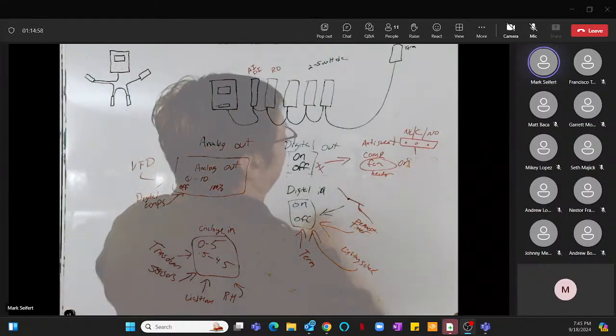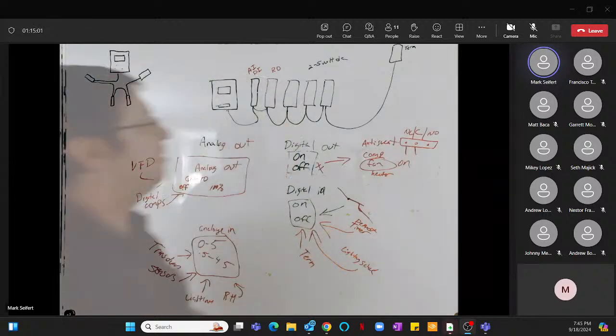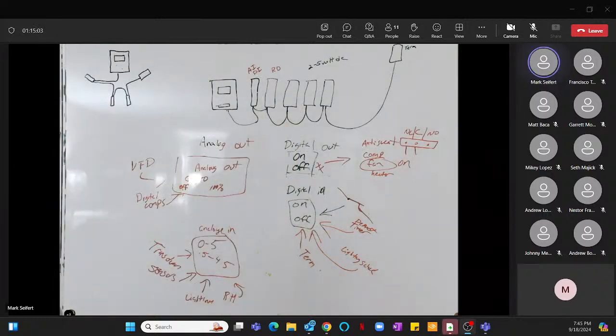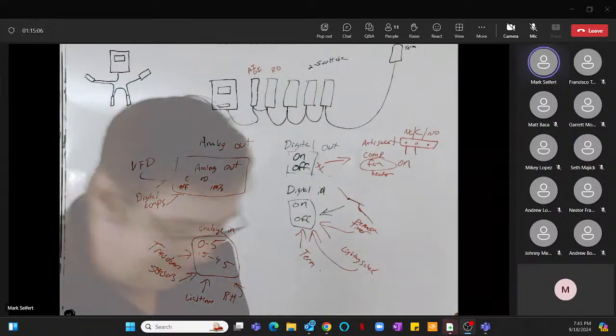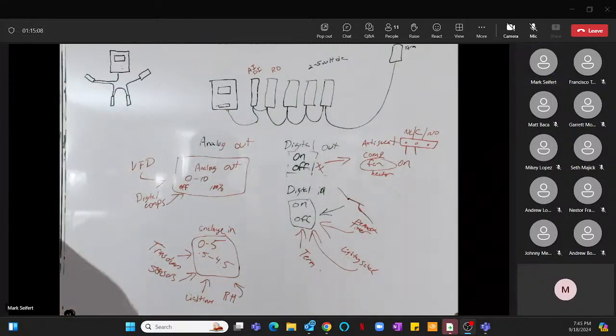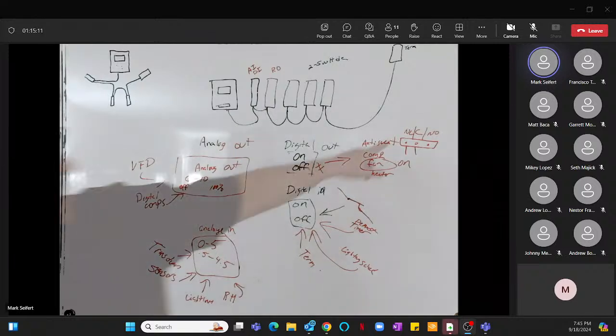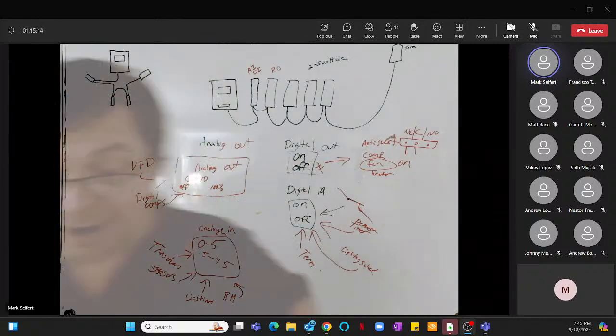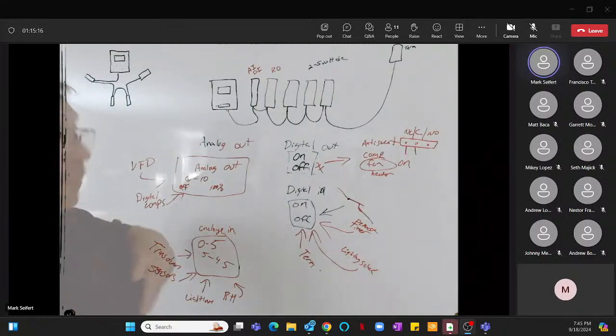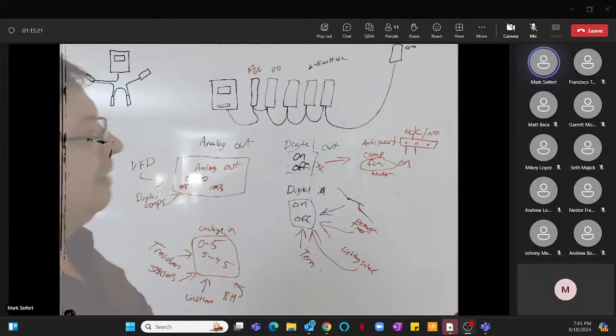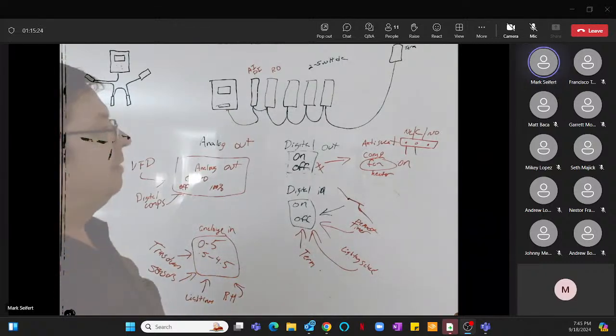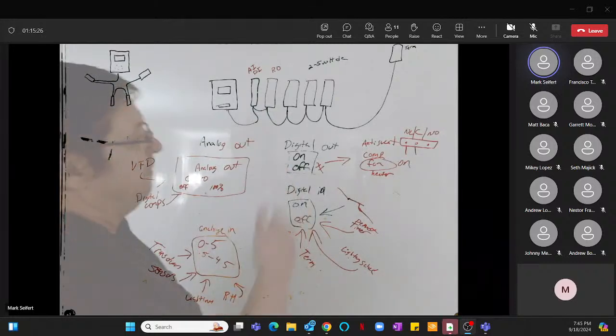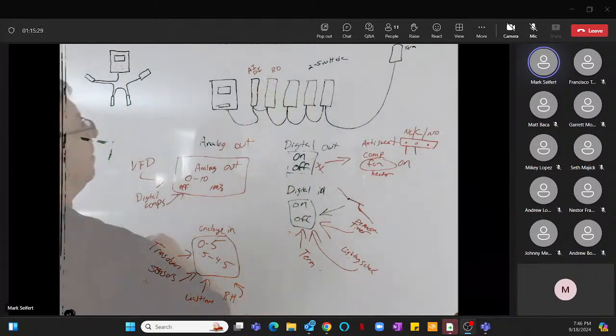What are the instances where a compressor does not always get wired common to normally closed? Every single protocol unit out there has half the compressors wired normally closed, half the compressors wired normally open. For a good reason. It doesn't have a switchback loop. It's not necessary. It's literally done so that if you lose the board, your RO board, only half the compressors come on.